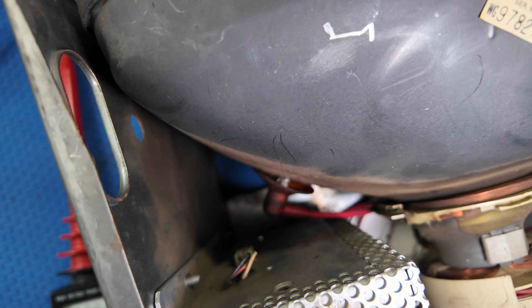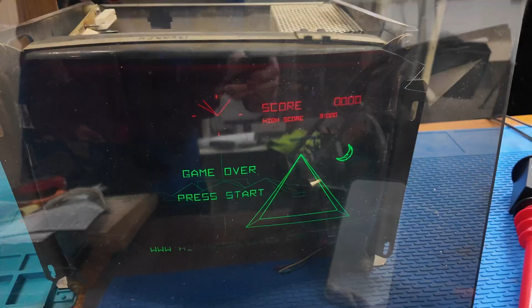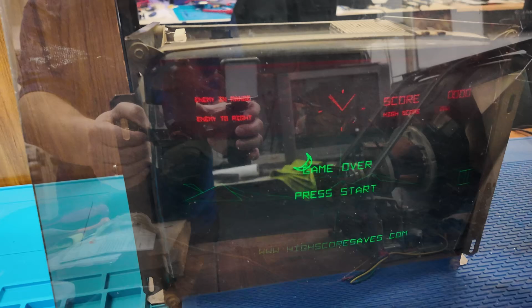I previously mentioned that the anode suction cup didn't seem to be securely on the side of the monitor. And so now when I look at it, I can see that it looks like one half of the anode clip is not in the monitor. So this could be affecting our picture. After fixing the loose anode cup, the lower intensity vector lines do look a little bit better. A better test might be to put the smoky plexiglass in front and then see how it looks. So with the plexiglass in place, it kind of looks like we're back to where we started from, maybe a little bit better.